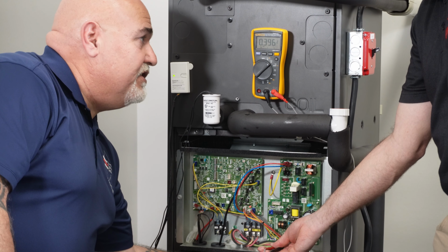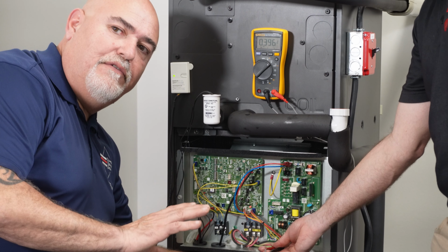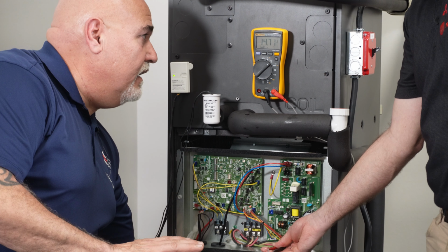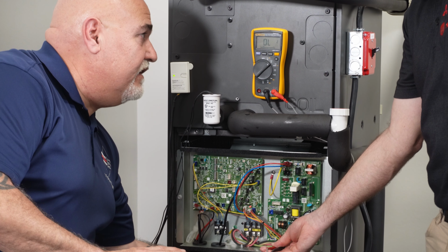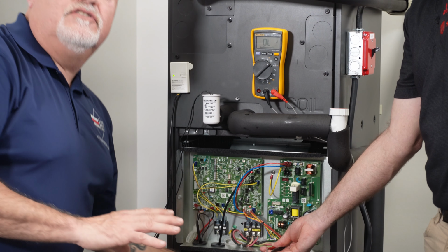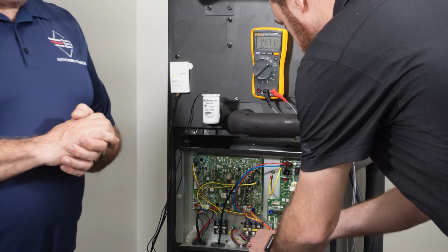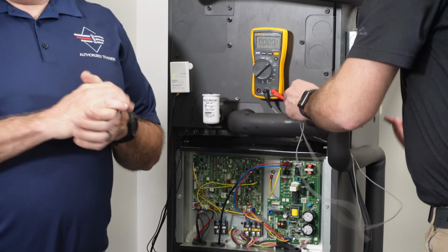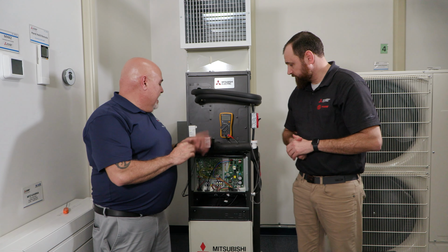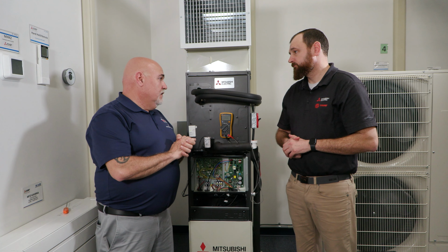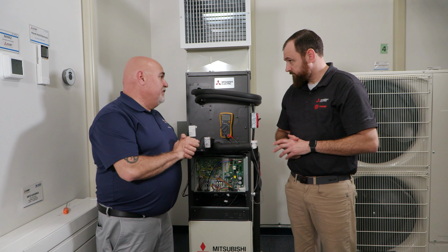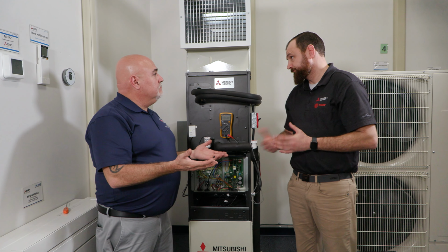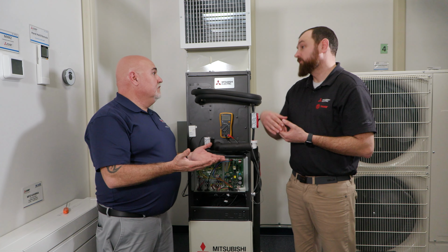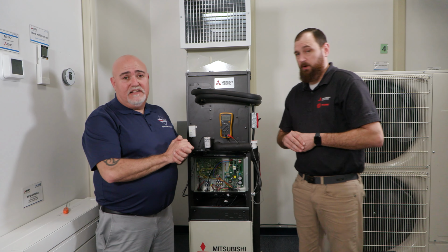We want to spin that blower wheel very slowly, just turn it gently, and there's our rotational feedback. That tells me this system is functioning properly. We have that rotational feedback. In this case, if this system was in error, which it isn't, if it did have a rotational feedback error code and we had rotational feedback coming out of the motor, what's bad? If we have rotation coming out of the motor, then the board would be bad, exactly.